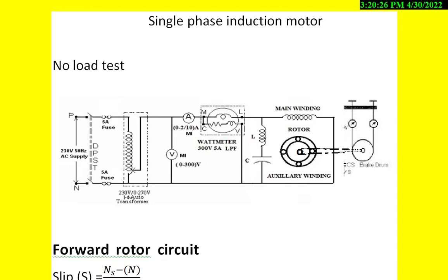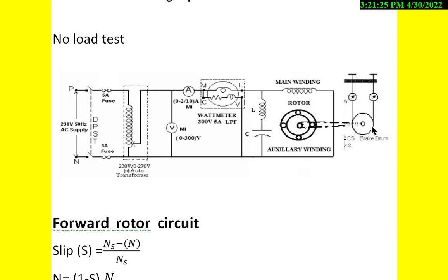Let me summarize the no load test and blocked rotor test conduction on the single phase induction motor. For conducting these two tests, the arrangement is as shown. There should be a single phase AC supply, an auto transformer, a voltmeter, an ammeter and a wattmeter, and this is the auxiliary winding branch, and this is the main winding branch. This is the rotor, and the rotor shaft is coupled to the pulley like this, and the pulley carries the rope, and the rope carries the two spring balances, and the rope is connected to the beam, and the beam carries the two adjustment knobs to adjust the rope condition on the pulley.